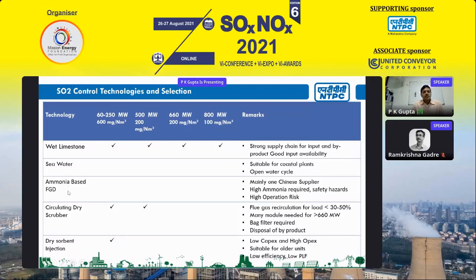Then comes ammonia-based FGD. Vendors are limited here, mainly one Chinese vendor. It requires a high amount of ammonia, so there's some safety hazard and high operation risk, and cost increases if the byproduct isn't sold.